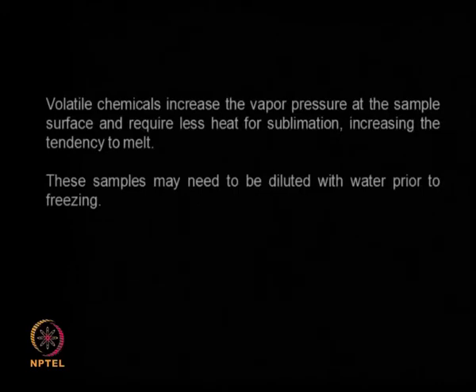If volatile chemicals are present, they increase the vapor pressure at the sample surface, and we need less heat of sublimation. The material may melt rather than remain frozen solid. If it forms a melted product rather than a frozen solid, it is not good. The solution is to dilute it with more water prior to freezing so that a solid ice forms — volatile chemicals always lead to problems in lyophilization.